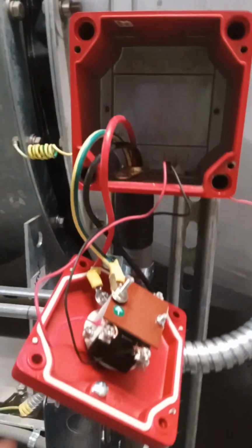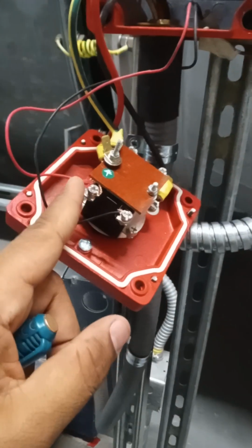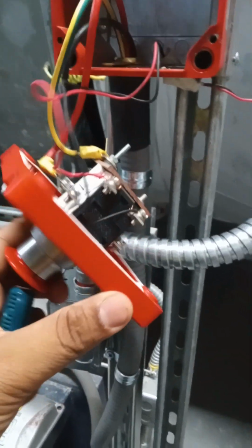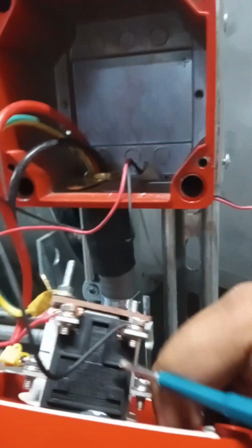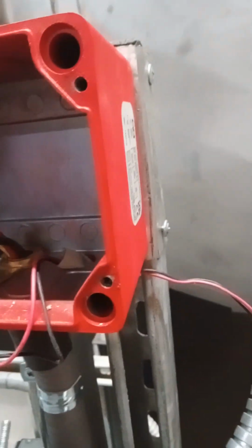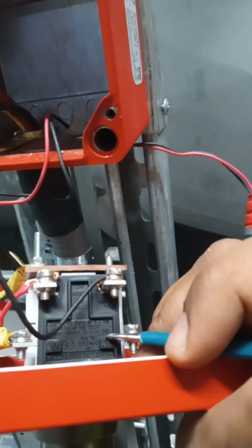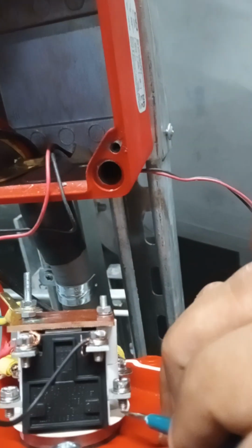This is an emergency stop button, so the connection shall be NO. So here these two cables shall be NO, normally open. And these two are normally closed, the normally closed terminal. So it is mentioned here normally open. Here it is mentioned NC, that bottom side. NC is mentioned here, these two are NC. NO is mentioned here, and here. NC is mentioned at these two places. So these are NO, and this bottom one is NC, this and this last one.